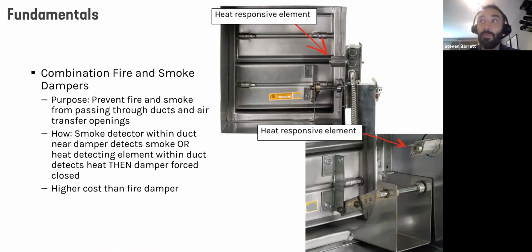So if your system was operating, we detect a fire, either the fusible link melting or the smoke detector detecting smoke, and the actuator or the spring starts to close, there may be so much pressure and velocity from the air flowing through the duct, it prevents the damper from closing. So typically it's best to always specify dynamic dampers. The cost difference is pretty marginal. And we'll actually get into a little bit of whether or not those units will be shut down when these dampers do need to close. So hopefully I answered the difference between the two. Thank you.